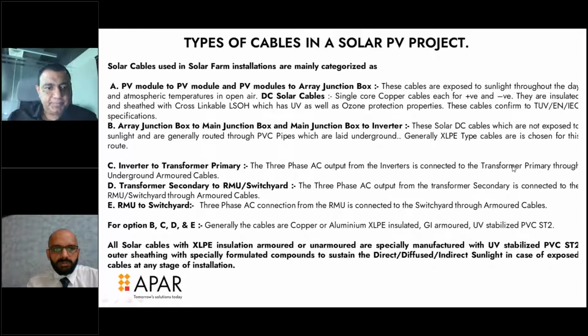Then you have the inverter to transformer primary cables, and the transformer secondary to RMU switchyard cables. These are armored cables, either copper or aluminum, with PVC grade material since they are underground. All these cables are XLPE insulated, manufactured mainly with UV stabilization, a compound used to sustain direct, diffuse, or indirect sunlight exposure at any stage of installation.